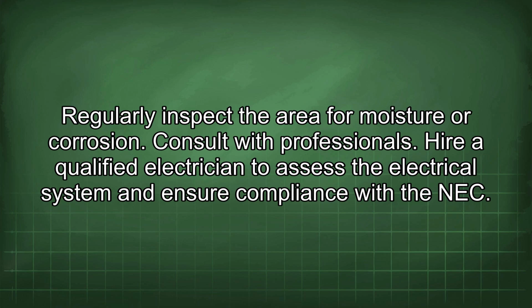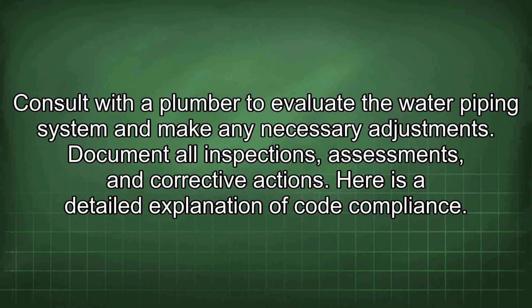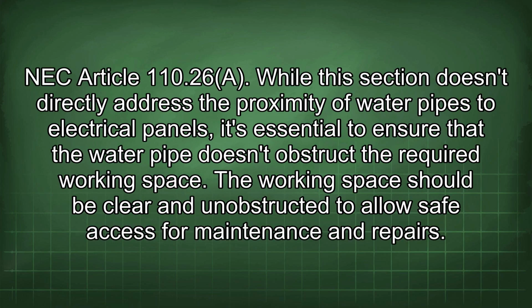Consult with professionals. Hire a qualified electrician to assess the electrical system and ensure compliance with the NEC. Consult with a plumber to evaluate the water piping system and make any necessary adjustments. Document all inspections, assessments, and corrective actions. Here is a detailed explanation of code compliance. NEC Article 110.26(A). While this section doesn't directly address the proximity of water pipes to electrical panels, it's essential to ensure that the water pipe doesn't obstruct the required working space. The working space should be clear and unobstructed to allow safe access for maintenance and repairs.